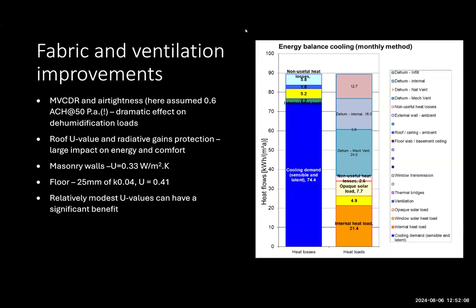So those are the key things: solar protection, modest improvements to the U-value with a bit of insulation, and a super airtight building with mechanical ventilation with cooling and dryness recovery is the way to go. According to this model - a very simple high-level model at this stage - we can reduce that by getting on for three-quarters, but it's still quite high compared to the passive house criterion, at 74.4 kilowatt hours per square meter of cooling demand.